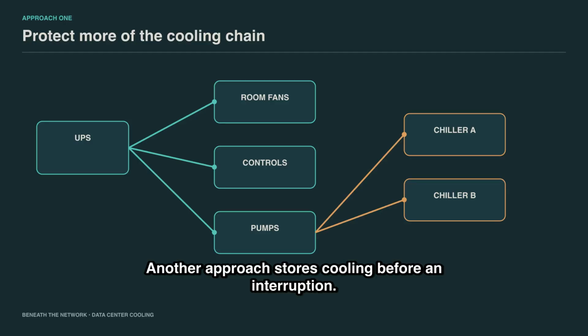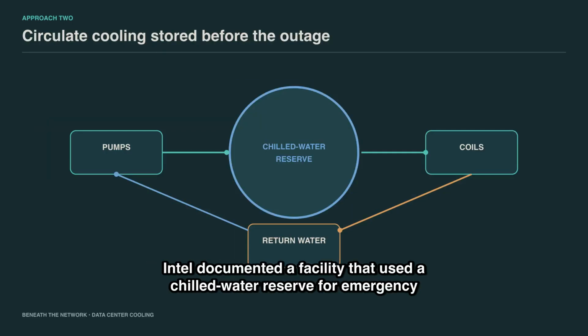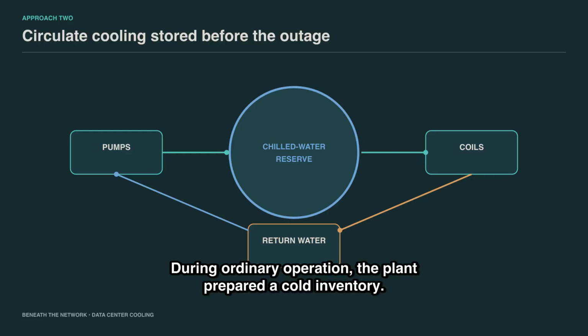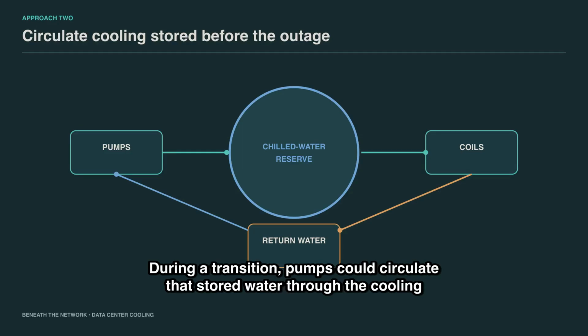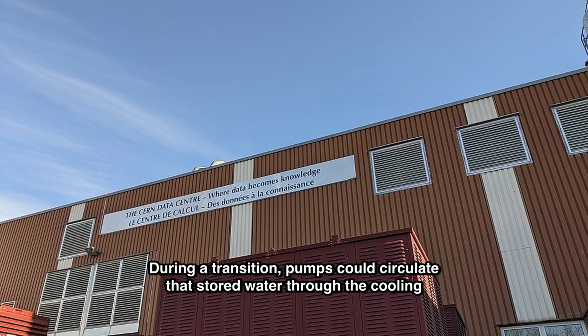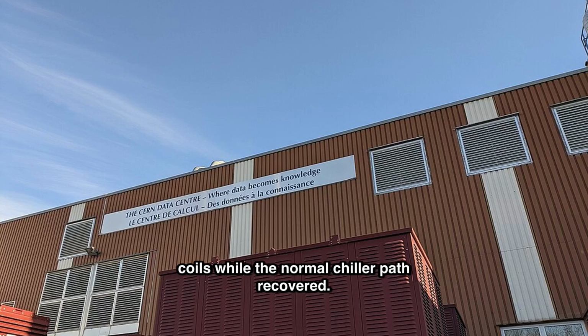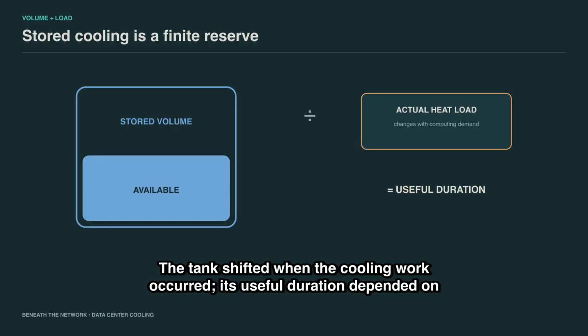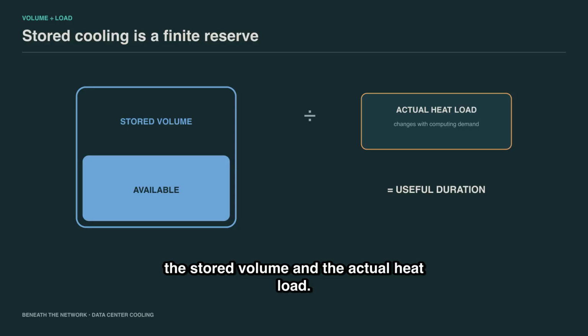Another approach stores cooling before an interruption. Intel documented a facility that used a chilled water reserve for emergency cooling. During ordinary operation, the plant prepared a cold inventory. During a transition, pumps could circulate that stored water through the cooling coils while the normal chiller path recovered. The tank shifted when the cooling work occurred. Its useful duration depended on the stored volume and the actual heat load.